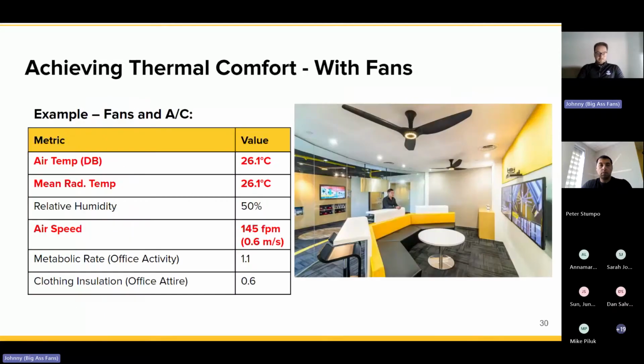Because now what we can do with fans is raise that set point a few degrees. Every degree you raise is usually about 3 to 6% electricity savings. And that's from the Department of Energy. So if you can do that, you are doing your building a service. You are helping the owner of that building save some money, and you're also helping the environment. So we're pushing that envelope a little bit. We're going to raise that set point.